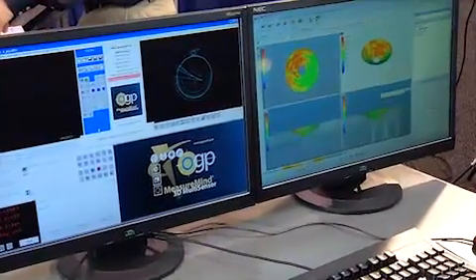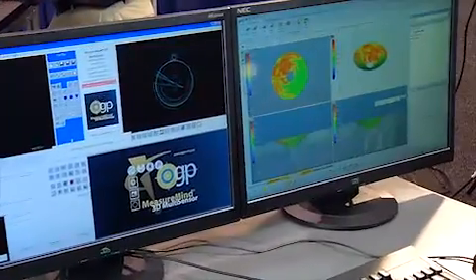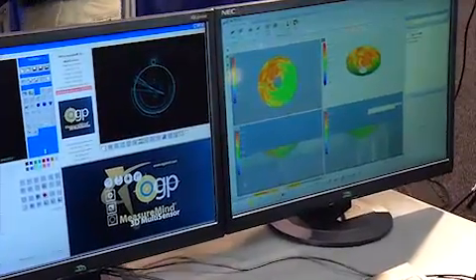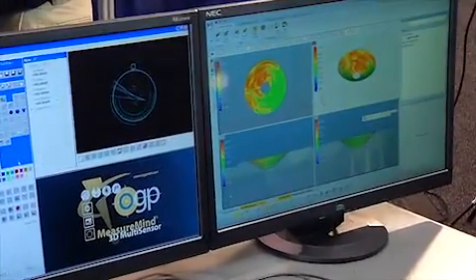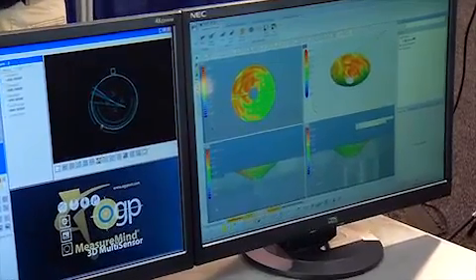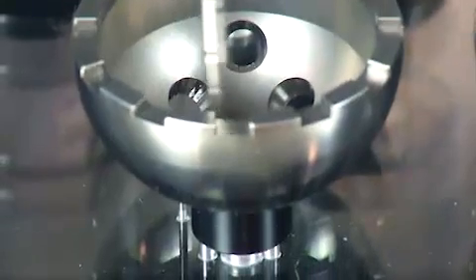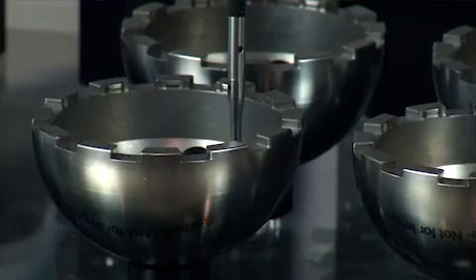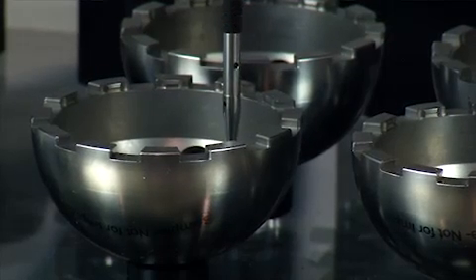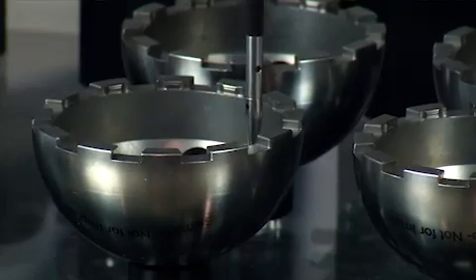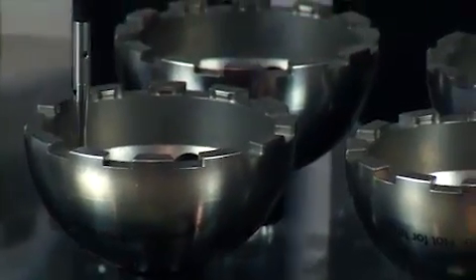The data can also be overlaid onto a 3D CAD model, and color maps as well as GD&T analysis can be performed for feedback for the production process. Here it's doing multiple scans on spherical and cylindrical surfaces to establish cylindricity, taper, sphericity, and the relationships between the geometries.